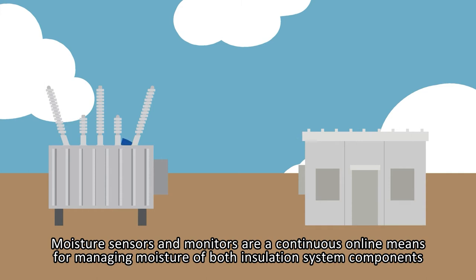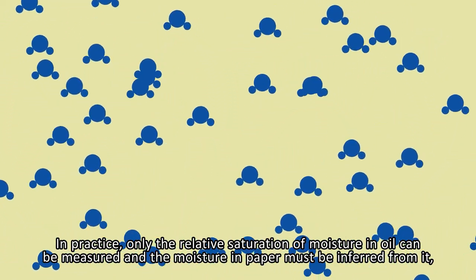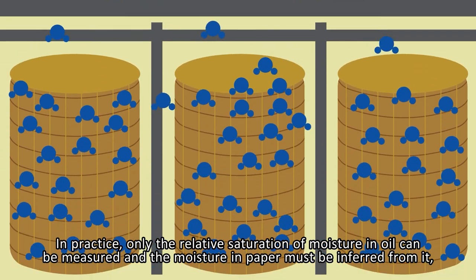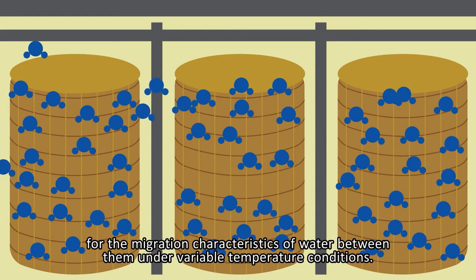Moisture sensors and monitors are a continuous online means for managing moisture of both insulation system components. In practice, only the relative saturation of moisture in oil can be measured and the moisture in paper must be inferred from it, based on the water absorption characteristics of both oil and paper and time taken for the migration characteristics of water between them under variable temperature conditions.